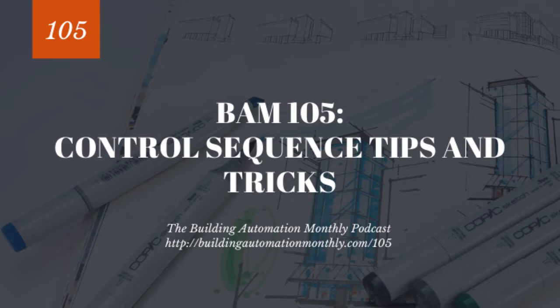What I mean by this is, if you look at a sequence and it's fairly simple, maybe a rooftop sequence: install a BACnet IP interface card, schedule occupancy on and off, turn setpoint on and off. Then the labor for that is going to be a lot less than for an air handler sequence where you've got a fan wall that you need to control, you've got exhaust and return VFDs that are in a control sequence where you need to compare the two, and then you have airflow monitoring stations, and oh, by the way, you have an enthalpy wheel, and you also have a building static strategy that is tied to these exhaust fans. You're starting to see where I'm going. That is going to be a much more complex sequence.